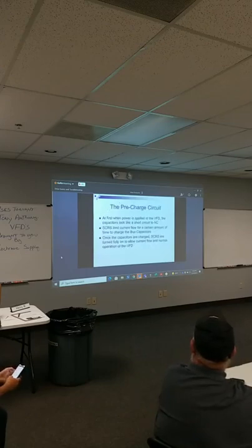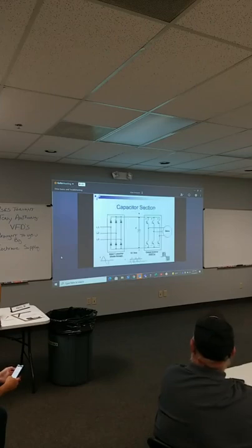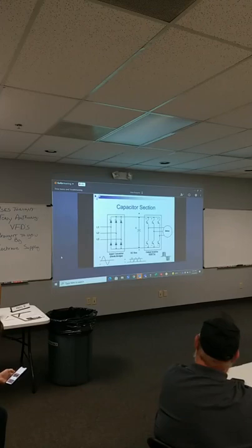Pre-charge circuit, we already went through this about the capacitors, limiting the inrush. Now we get to the capacitor section. This is the power, this is that DC bus. If you ever see it on any drive, down at the bottom, there should be a plus and minus, and sometimes you'll have two or three pluses and two or three minuses. That is the plus and minus of your DC bus. And that's what the capacitors create, that DC bus. And once again, rule of thumb, 1.44 times your incoming voltage is what you should see between that plus and minus on your ohm meter when you're checking your DC bus voltage.